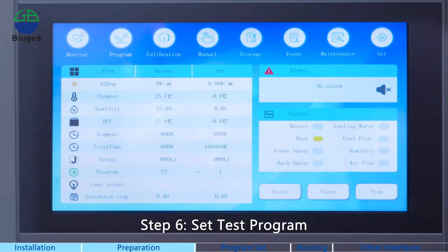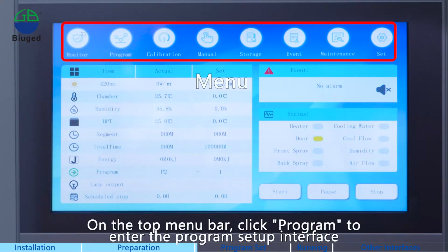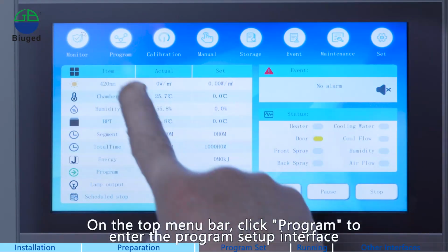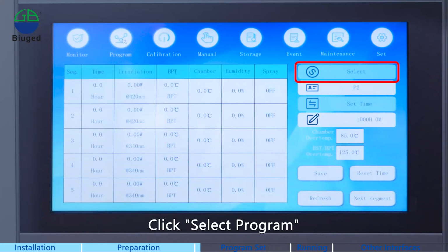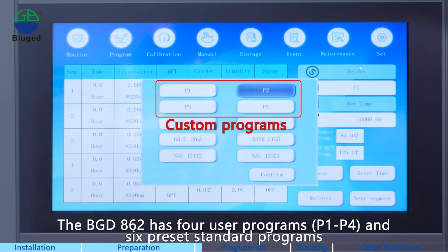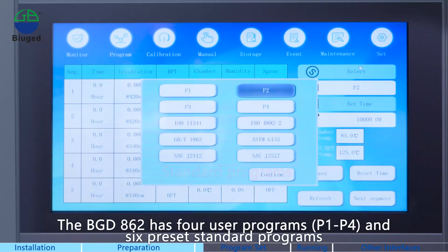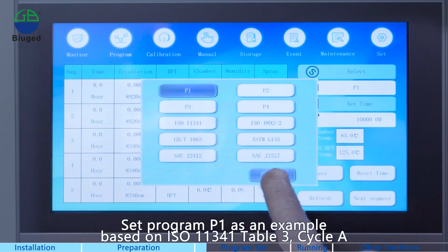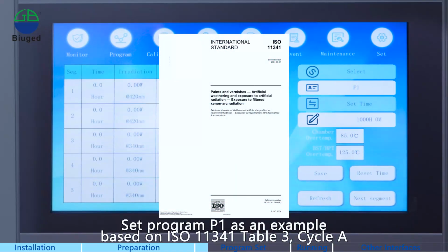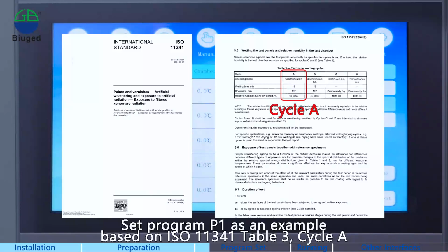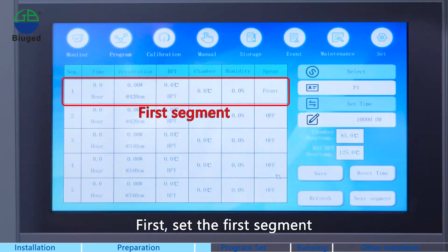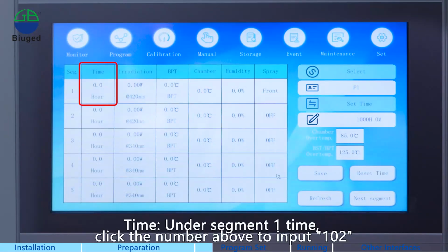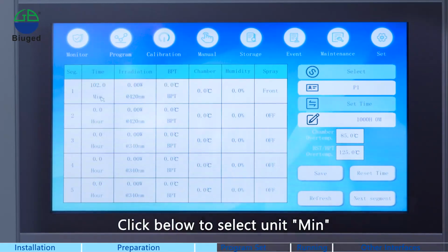Step 6. Set test program. On the top menu bar, click Program to enter the program setup interface. Click Select Program. The BGD 862 has 4 user programs and 6 preset standard programs. Set program P1 as an example based on ISO 11341 Table 3, Cycle A. First, set the first segment. Time, under Segment 1 Time, click the number above to input 102. Click below to select unit minutes.